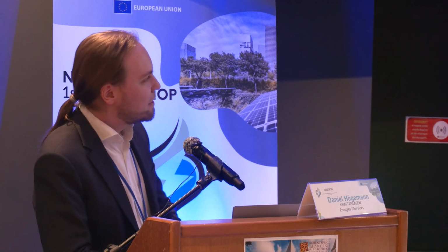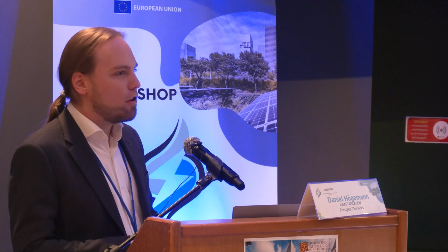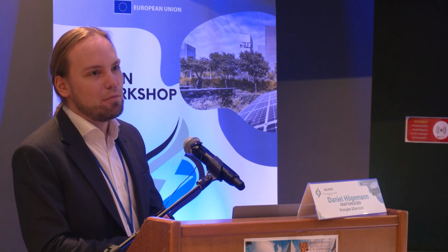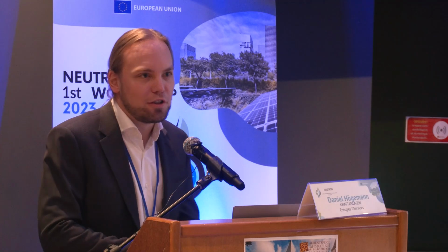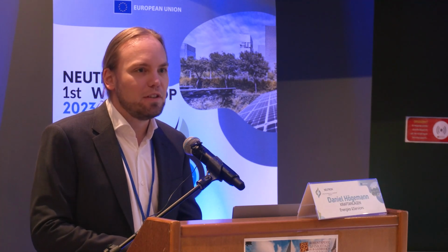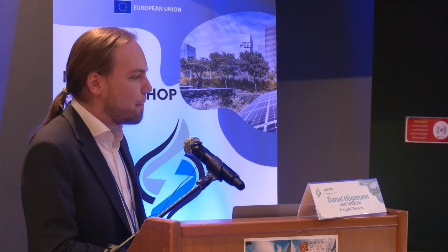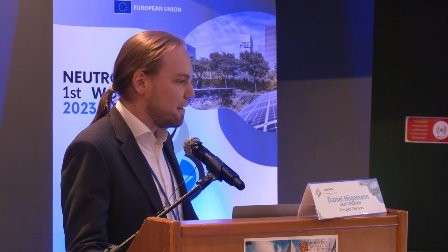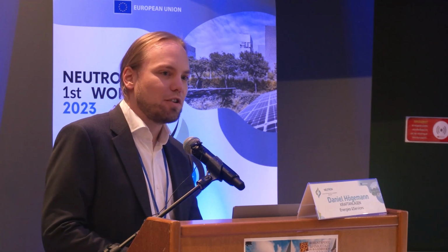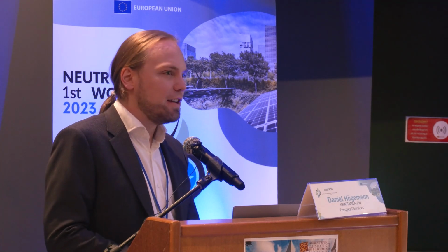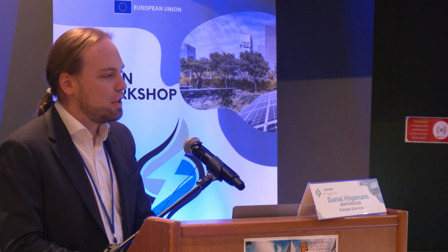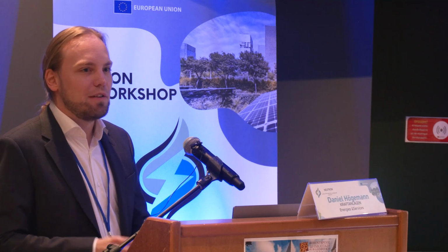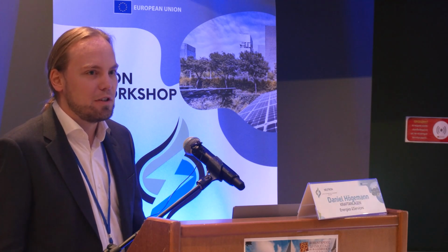So the green heat module itself is basically the core component which has been developed by Kraftanlagen, the technology, for about 15 years now. Basically, it converts intermittent renewable energy sources via electric heaters to heat at temperature ranges between 750 and up to 1000 degrees Celsius.